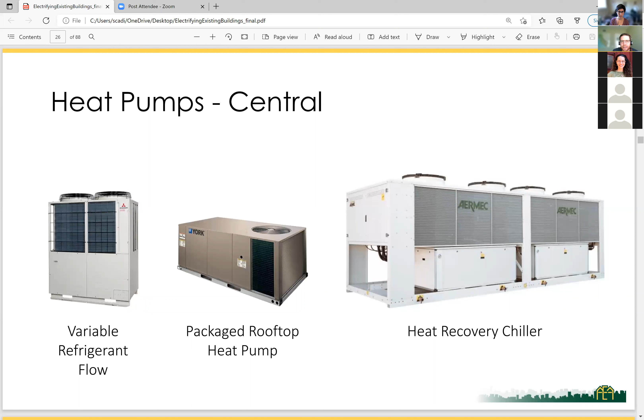There are also heat pumps for larger commercial applications, or for a whole building HVAC system in a multifamily building. Examples include variable refrigerant flow and package rooftop heat pumps, which look just like package rooftop air conditioners or furnaces, but are now all electric and provide high efficiency space heating and air conditioning. If a building previously had a big chiller providing chilled water and a boiler providing hot water for heating and cooling, you can instead get a heat recovery chiller—basically a chiller plant that does both heating and air conditioning.